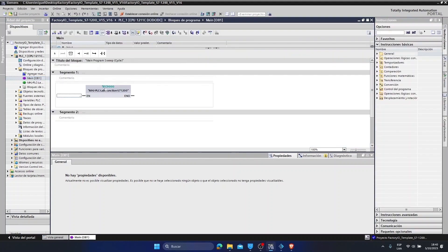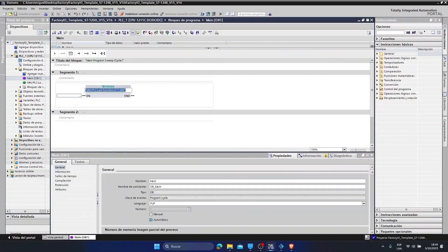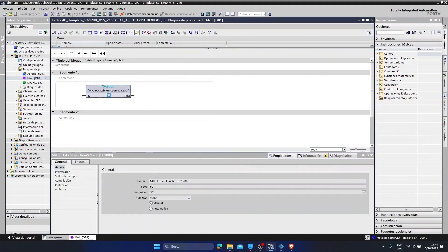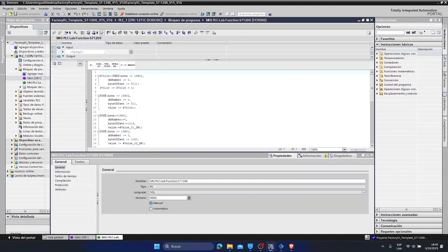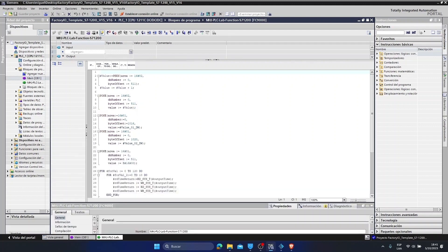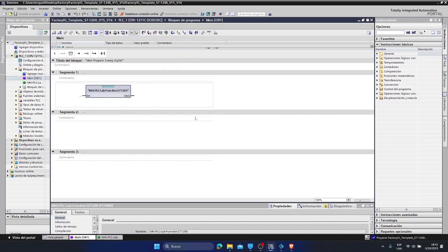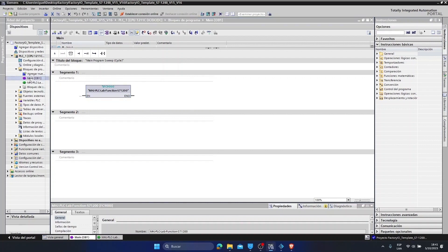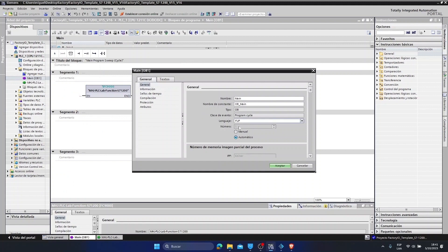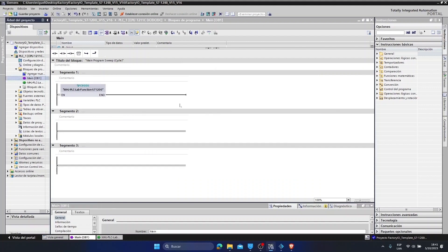This would be the block. If we double-click on it, it will direct us to the programming that is used to carry out the communication between the TIA portal and the factory. This programming is done in SCL code and we do not have to modify anything here. We simply leave it like this with this code, with this FC block. Now it is in another language. I am going to change it to the ladder language that is the one with which we program PLCs the most. So we are going to change the ladder language, then we go to properties. Now there is the FUP language. I am going to change it to the LAD language.